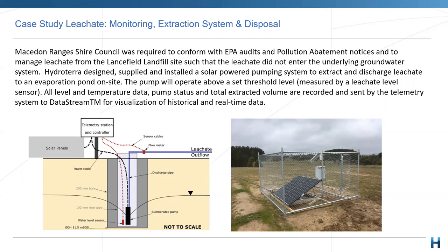Yeah. What's the maximum flow rate you get out of that? It really depends on the pump as well. We put in a pump, I think it's pumping 30 liters per minute or so, but these bores are kind of low yield, they don't produce a lot of leachate. It's typical that we talk about 1 or 2 liters per minute or even less. It really depends on the location. The new tender talks about 330 kiloliters a month. Yeah, so about 10 kiloliters a day. Right, kind of thing, yeah.